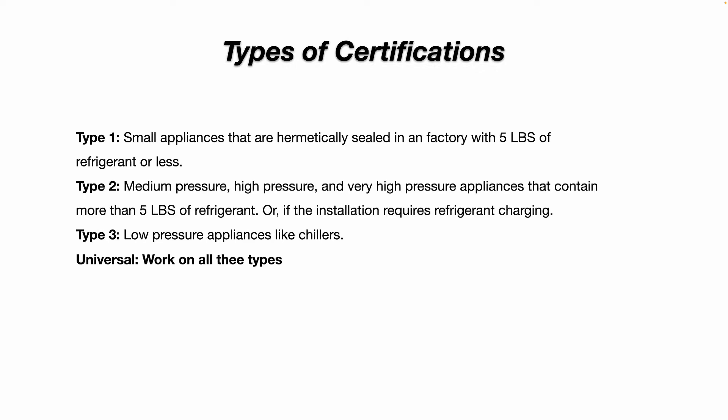The types of certifications are: Type 1 for small appliances that are hermetically sealed in a factory with five pounds of refrigerant or less — think refrigerators, window air conditioners, drinking fountains. Type 2 covers medium pressure, high pressure, and very high pressure appliances that contain more than five pounds of refrigerant, or if the installation requires refrigerant charging.